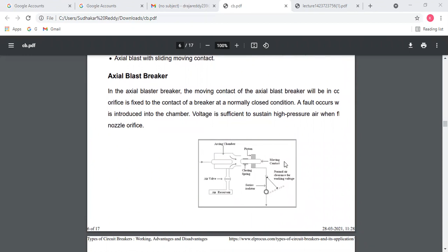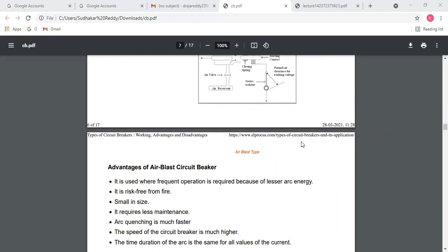So, now the advantages of the ABCB breaker. It is used where frequent operation is required because of lesser arc energy. It is risk free from fire. It is an air blast, no? So that's why it is risk free from fire. It is small in size. It requires less maintenance. Maintenance is very less. Arc quenching is much faster.